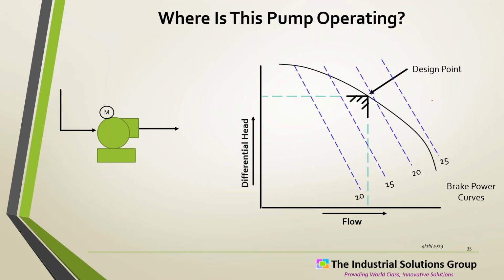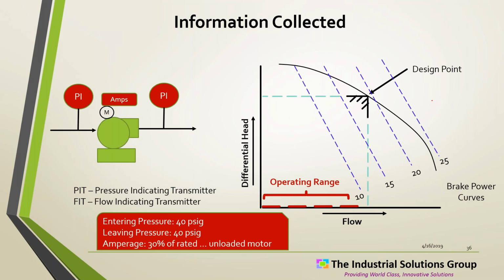But here I've got the pump, I've got no gauges, I'm flying blind, I'm looking at it. It's not making noise, it's running smoothly, the motor's spinning, and it always spins, and they've never had an issue. So I had them work on a weekend when they were down and throw in just a couple of pressure gauges and take an amp reading on the motor. And boy, when we did that, look at what happened.